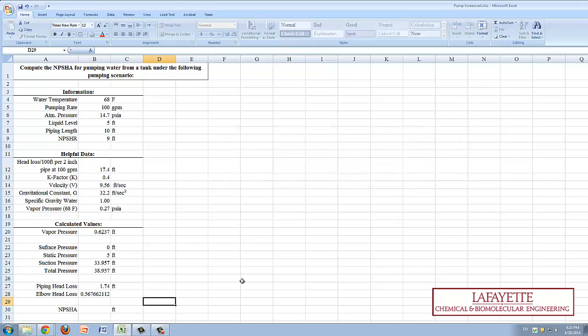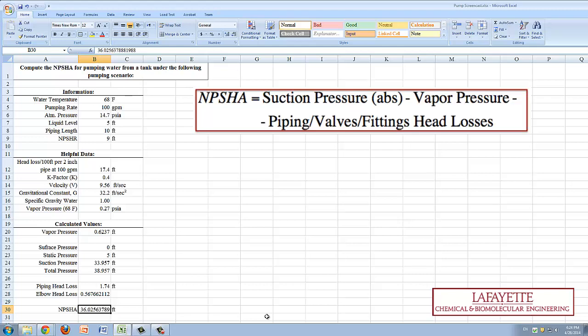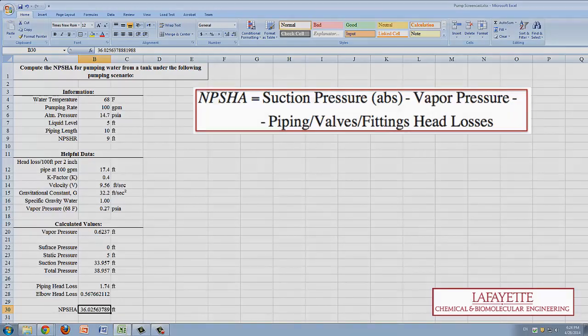Finally, the NPSHA is to be calculated via the equation shown. Since the value for the NPSHA is greater than that of the NPSHR, then the pump will in fact not cavitate.